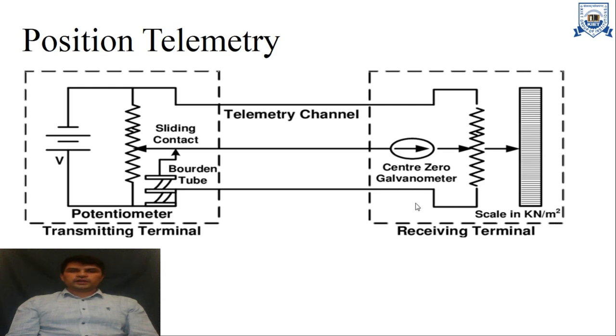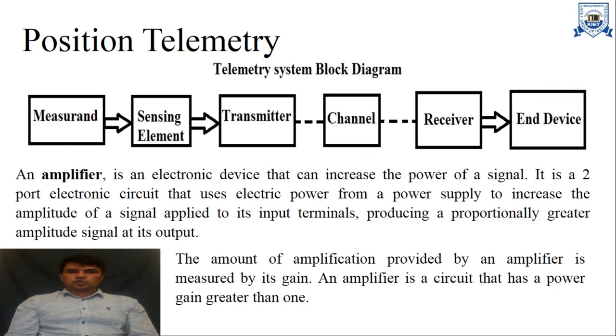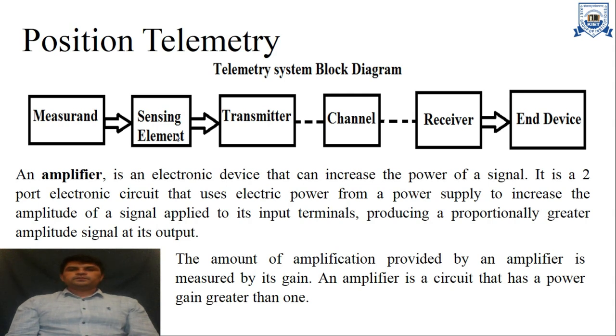There is also a potentiometer at the receiving end scaled in kilonewtons per meter squared, which is the unit of pressure. This is all about position telemetry, and in this case we use a wired channel. Here is the generalized block diagram of position telemetry. The measurand may be pressure, temperature, flow, or anything. Then there is a sensing element, which depends on the measurand — for pressure, we use a Bourdon tube.